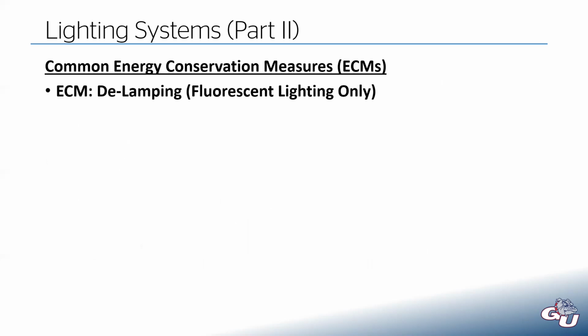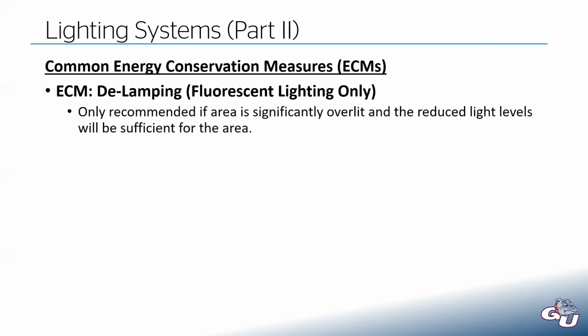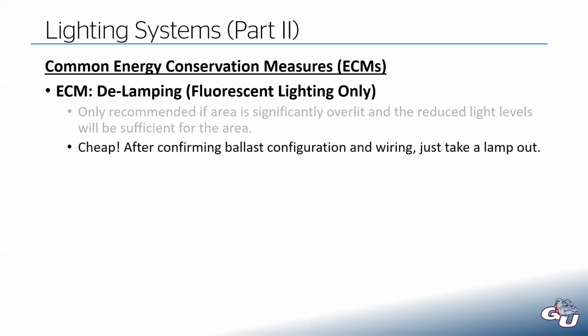Another thing you can do is called delamping, and this is for fluorescent lighting only. You have to use some caution with this. It's only recommended if the area you're looking at is already very overlit, with more light than it needs, higher foot candles than needed. If you do the math and decide to take out a lamp, you need to figure out what the new light levels will be and make sure that's sufficient for your customer. One big advantage of this is it's cheap.